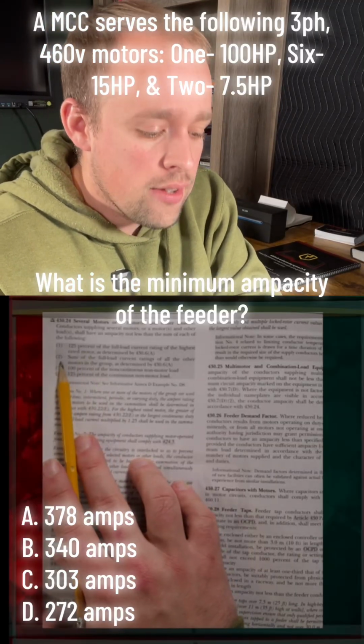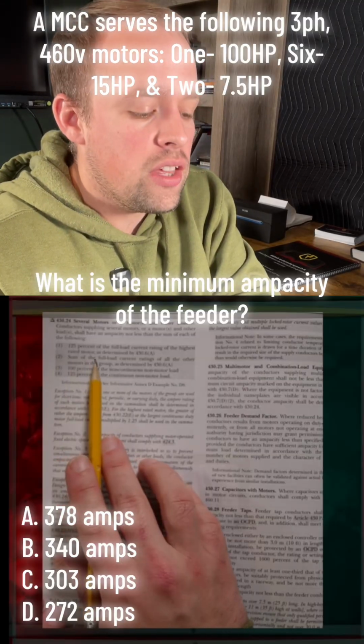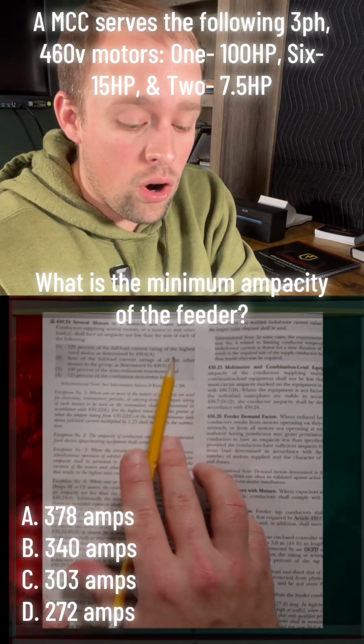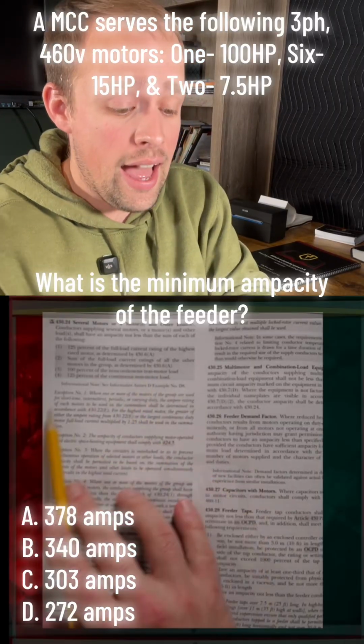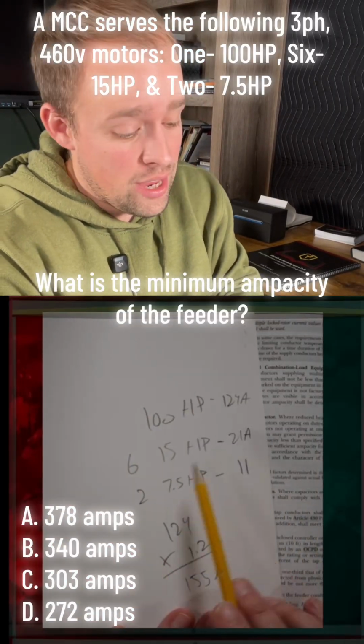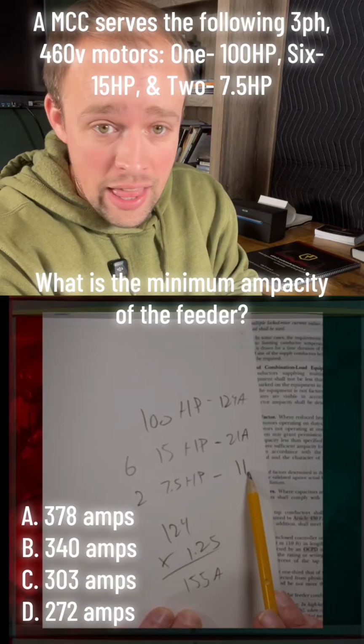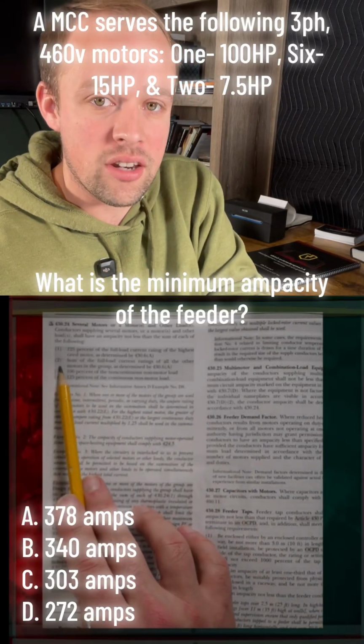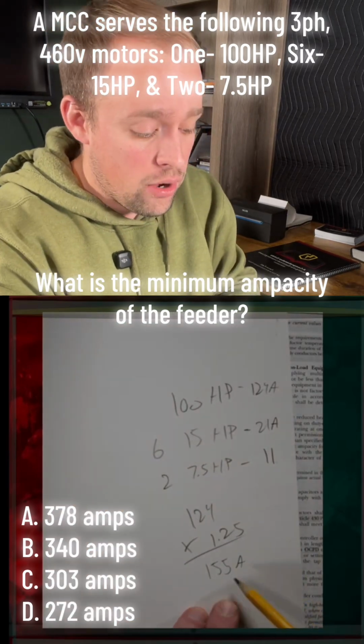And then number 2 says the sum of the full load current ratings of all other motors. So let me add 6 21s and 2 11s together. That will get me the ampacity for number 2, and then I'm going to add that to the 155 amps.